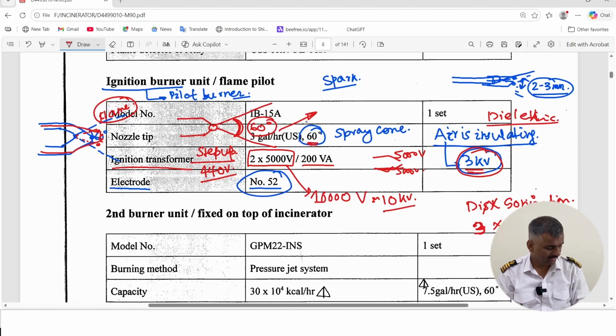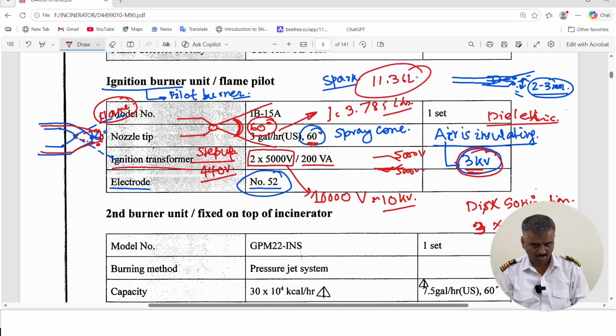If you see the gallon per hour, 1 gallon is approximately 3.785 liters of oil. So 3 gallons is equal to 11.36 liters. So approximately, the pilot burner is consuming 11.36 liters per hour of diesel oil. This is the study of the pilot burner, and the spray cone angle is a very important concept. Different nozzles have different spray cone angles, and there is a reason why you use a particular spray cone angle.